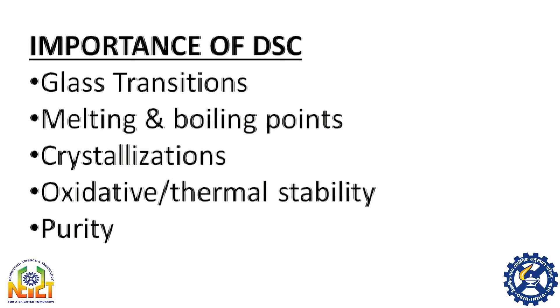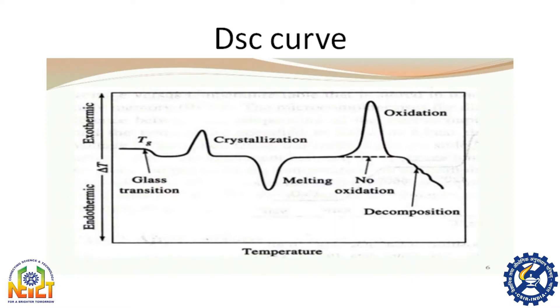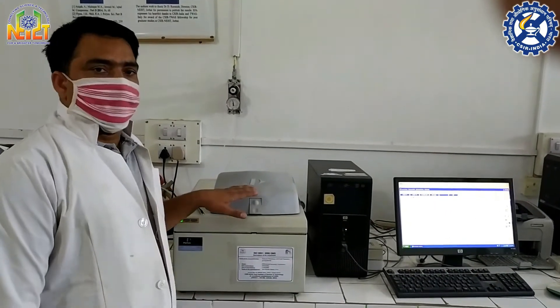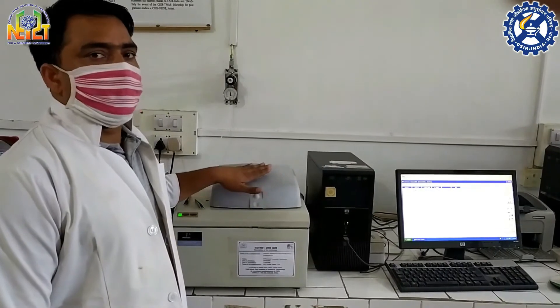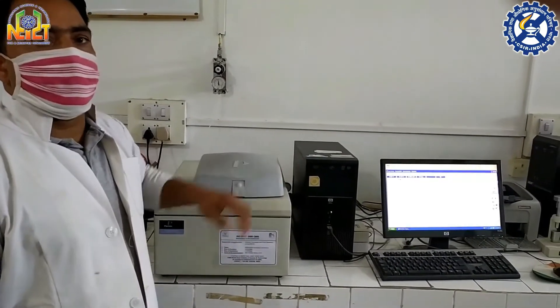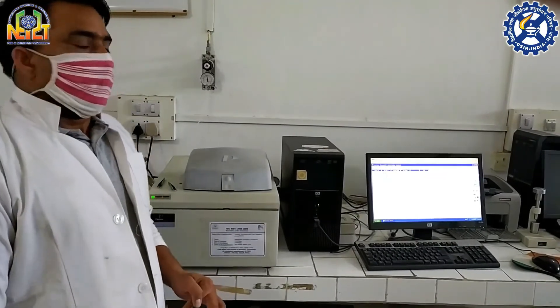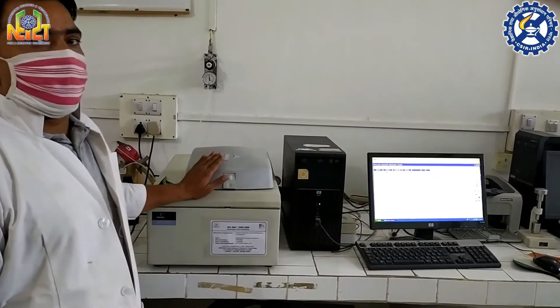What can DSC measure? We can measure glass transition, melting and boiling point, crystallization, oxidative thermal stability, and purity of polymers and other samples. DSC is a thermal analysis technique in which the sample is heated under an inert gas environment at a controlled heating rate, and this instrument gives us information about our polymer sample.